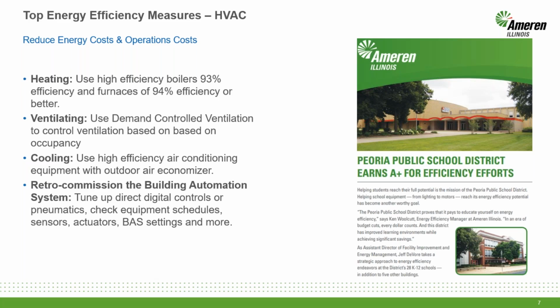And Peoria Public School District took a strategic approach to HVAC upgrades by focusing on those school buildings with the highest energy use first. They were able to replace inefficient window air conditioning units with high-efficiency central air systems, and downsize old inefficient boilers to smaller condensing boilers. And they tuned up their building automation system to better adjust occupancy schedules, occupied temperature set points, and unoccupied temperature set points. They also added variable frequency drives to their air handling units and pool pump and upgraded to LED lighting. So they hit on quite a few of the top recommendations.